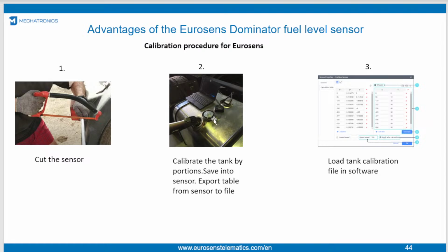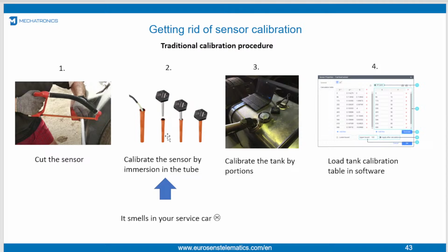As a result, we have tank calibration in a format we can upload to the GPS tracking platform, and in the sensor we have empty and full calibration, same results. So you don't need to bring this smelly calibration tube for installations when you are going to do real tank calibration by portions. But the tube is needed when you use another way of tank calibration, like mathematical calibration or loading an existing table. So you will do either sensor calibration in the tube or tank calibration by portions.